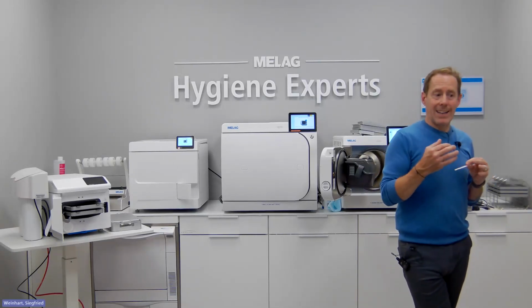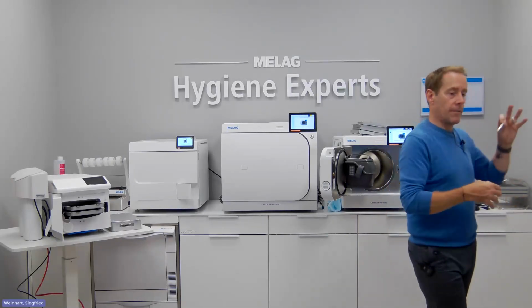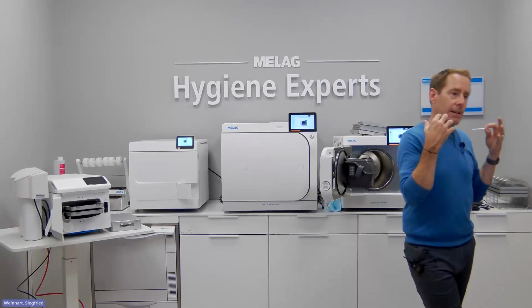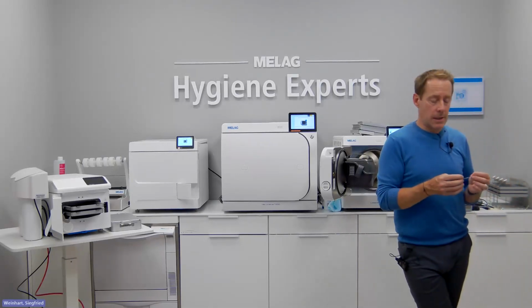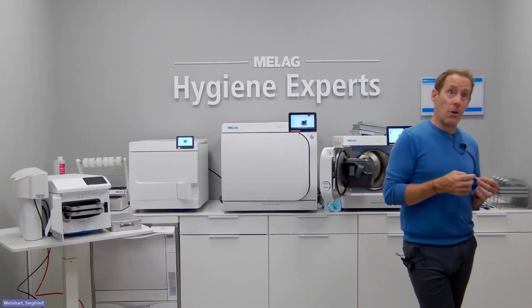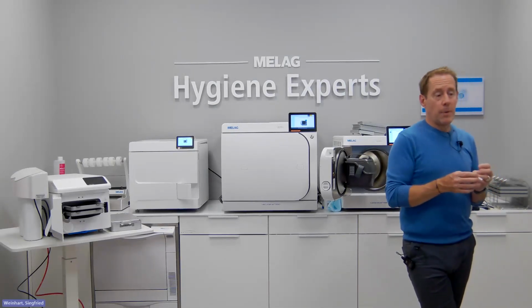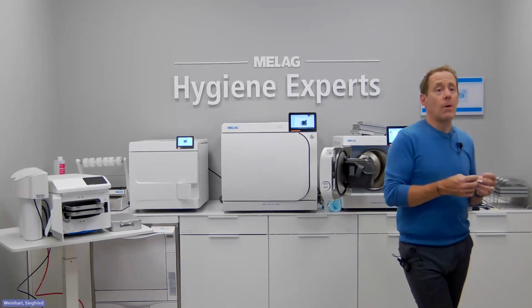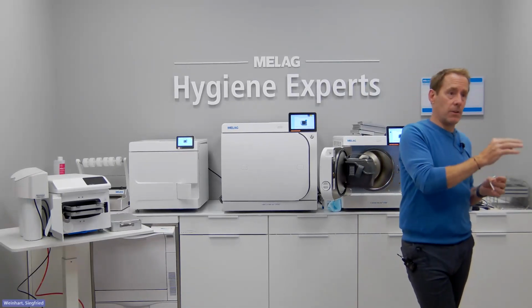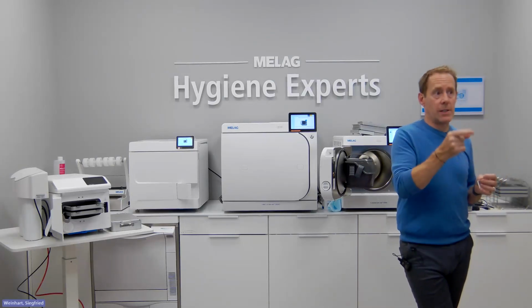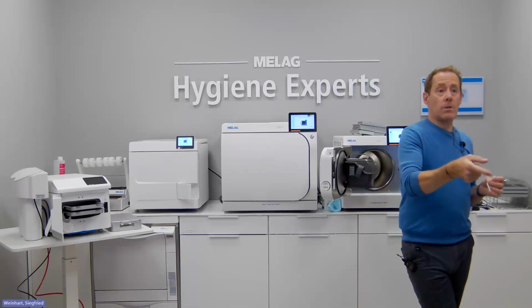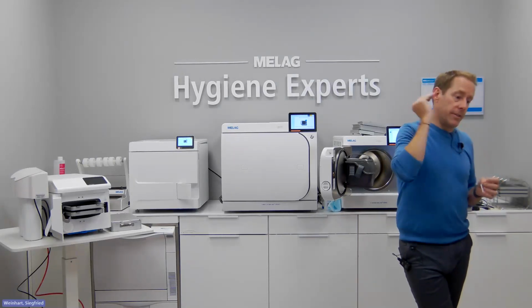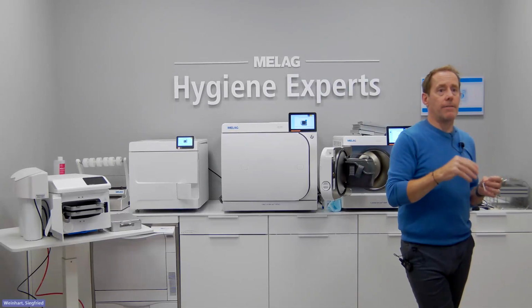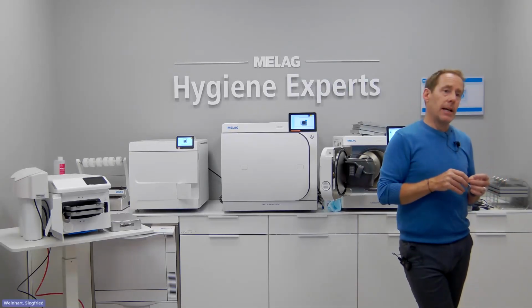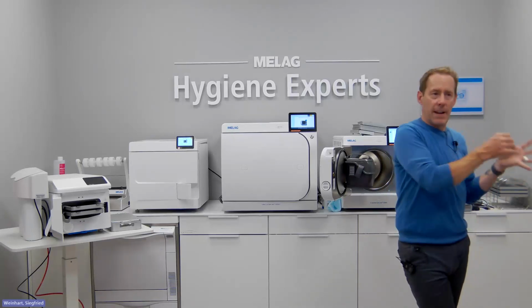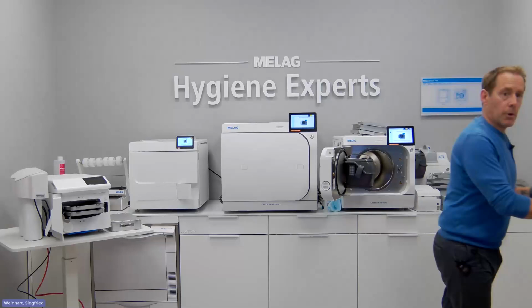So some manufacturers will stipulate that if you don't have a data logger, you should use a class 6. In terms of the regulations, HTM 01-05 and so forth, they don't necessarily stipulate that - you're following manufacturer's guidance. The easiest, most cost-effective thing if you don't have a data logger is that there are companies that will retrofit data loggers onto the unit, or if that's not possible, retrofit at least a printer onto it. So it might be worth looking at that. If you message me your details and tell me what unit you've got, I can find out if it can be retrofitted, because over the long run that could be more cost effective for you. That's something we can help you with.